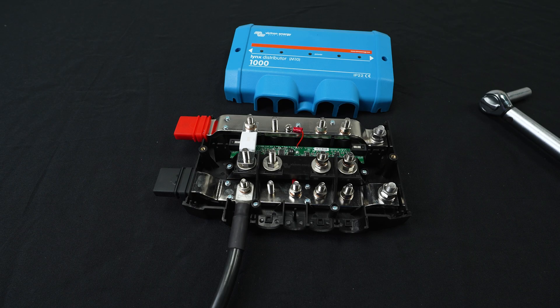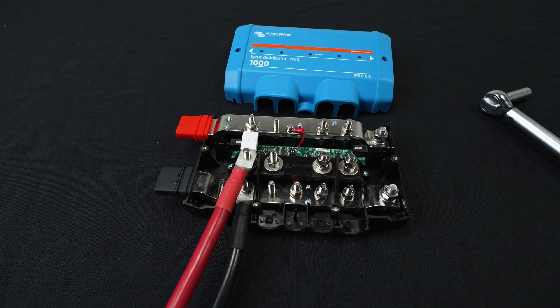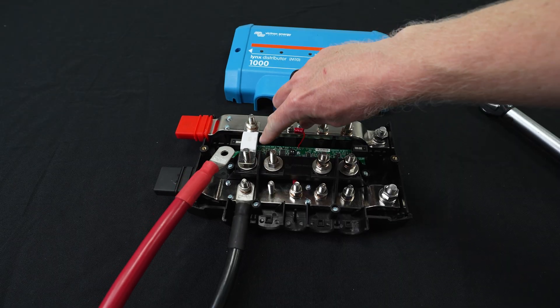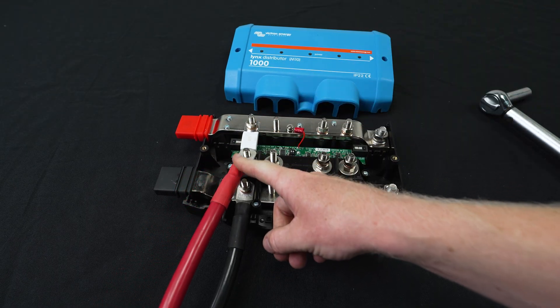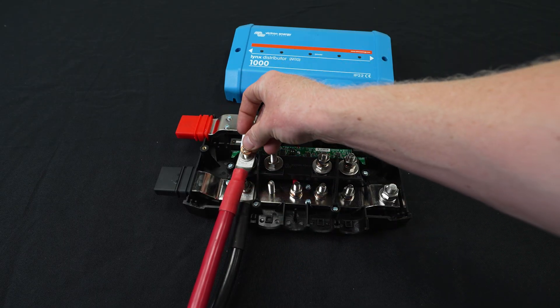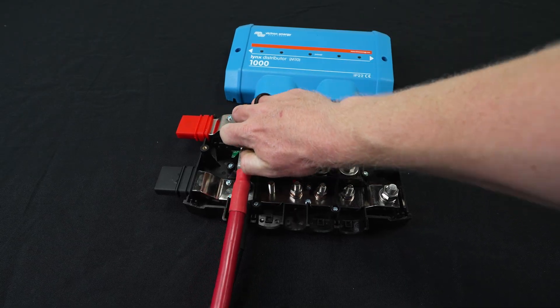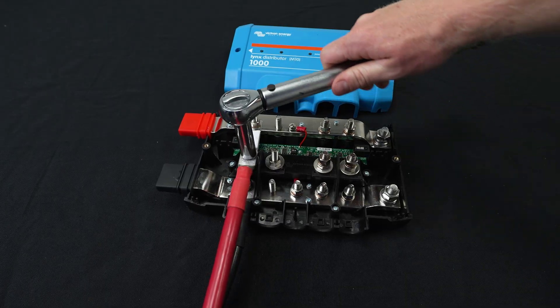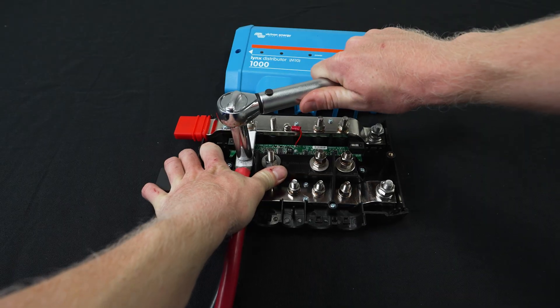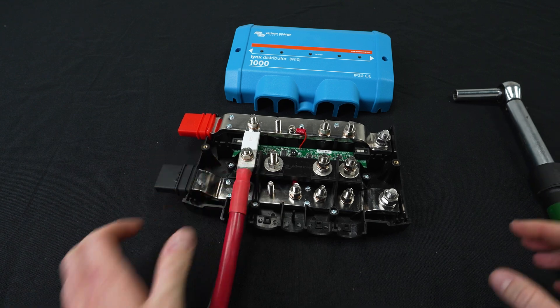Now we're going to go ahead and land our positive cable. Again this is a 2 AWG cable, 5/16 lug. So the fuse is acting as our current carrying conductor here. So again wire right on the fuse, no washers in between the wire and the fuse. On top we have our flat washer, our lock washer, and our nut. You'll notice your cable wanting to rotate, so sometimes it helps to hold your cable in place while you're tightening.